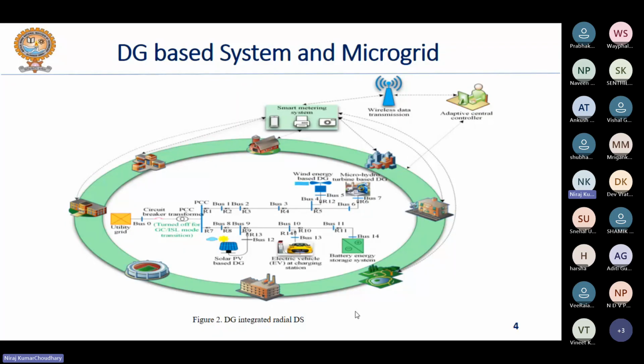So the basic difference is that whenever there is a fault in the upstream network, meaning at the higher voltage side of the network, towards the utility grid side, one of the essential requirements for the microgrid is that it should isolate itself from the upstream higher voltage networks, right? So that the fault cannot propagate to the microgrid side, right? That mode of operation is known as islanded mode of operation.